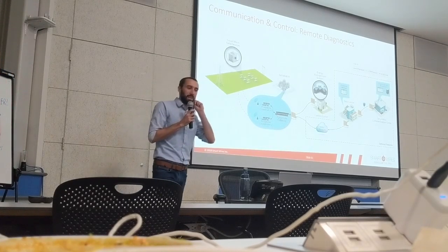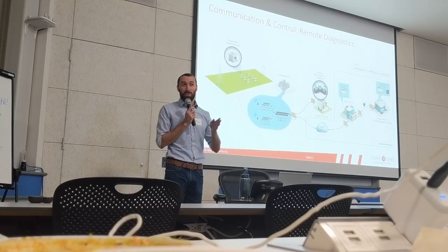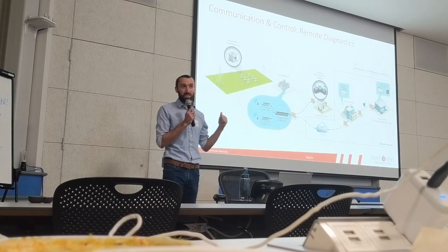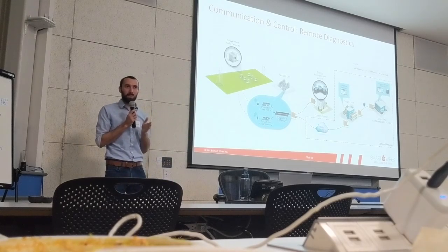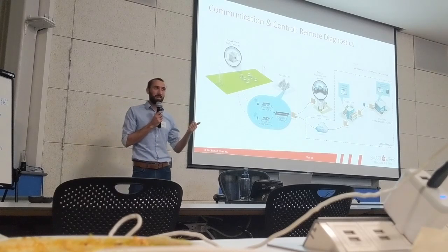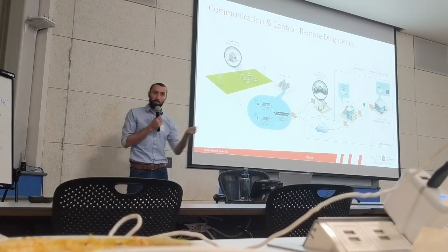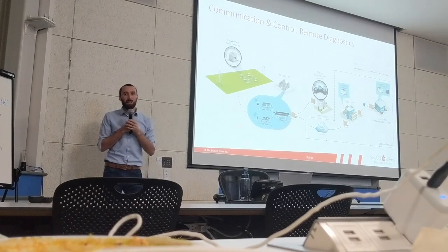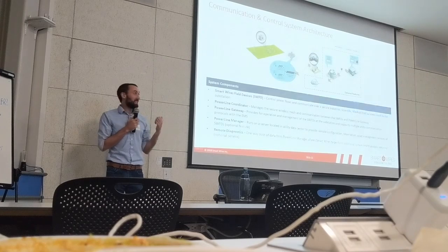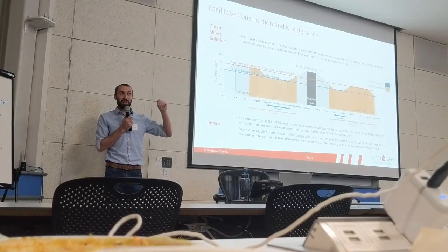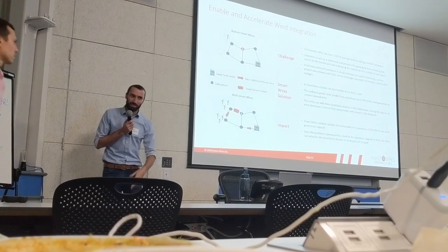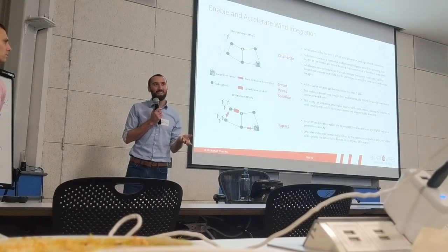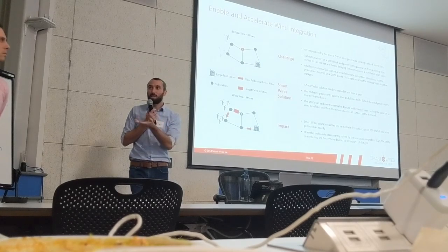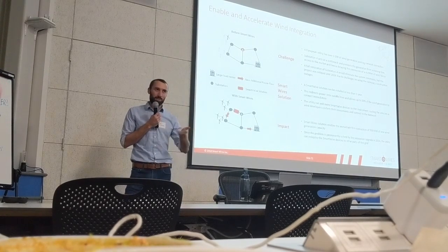Yeah, I'll start and Brock can jump in. The main limitation on the distribution system is those 12 kV lines — they're almost never in a mesh network. What's key about our devices is you need an electrically parallel path to push power onto most of the time. There are some things we can potentially do in capacitive mode with our devices on the distribution system, if you're trying to pull power onto a line that's not completely overloaded — there may be an application there. But we've found the vast majority of that network is radial; you don't have anywhere to push or pull power to. And in terms of cost, if you're deploying our devices at the transmission level, you're able to push and pull a lot more power. If you're on a 12 kV line serving a handful of homes, it's hard to make that cost-benefit work for installing one of our devices there. As Brock mentioned on our roadmap, that's where we want to get to eventually — a cheaper device that can work at those levels.